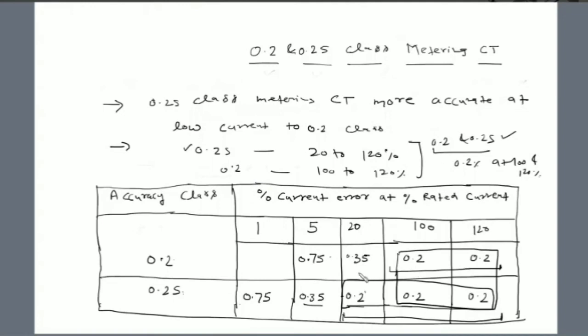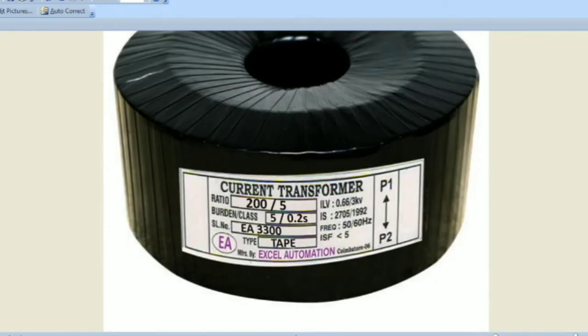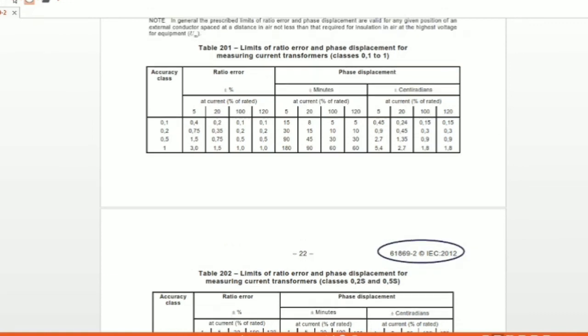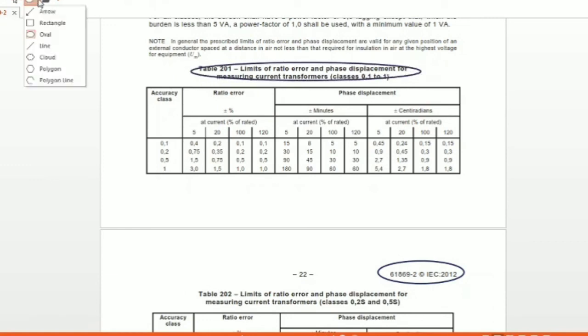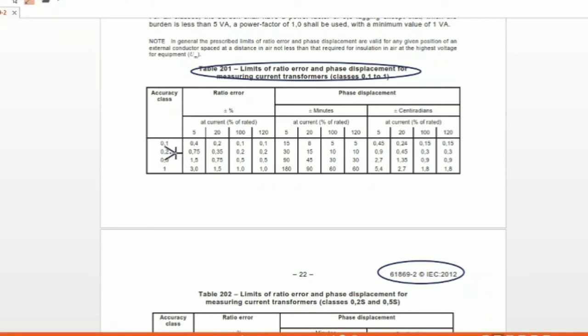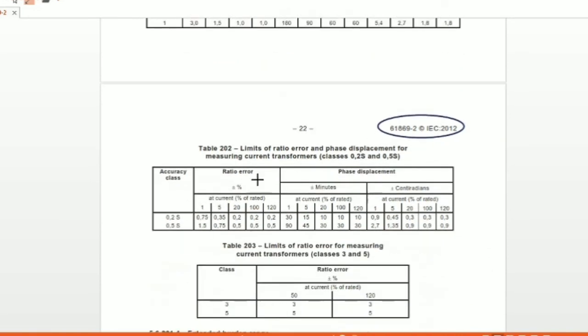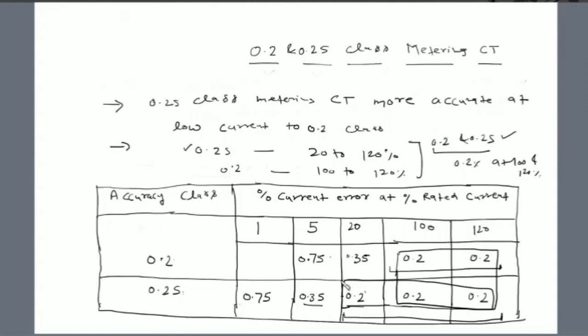Whatever we have discussed, this table can also be studied through IEC 61869. The reference is Part 2, pages 21 and 22, Table 201. In Table 201, for 0.2 class CT the current errors are 0.75, 0.35, 0.2, and 0.2. There is also phase error alongside current error. Similarly for 0.2S class CT, the values are listed in Table 202. In the next session we will discuss the difference between P and PS class protection CT.